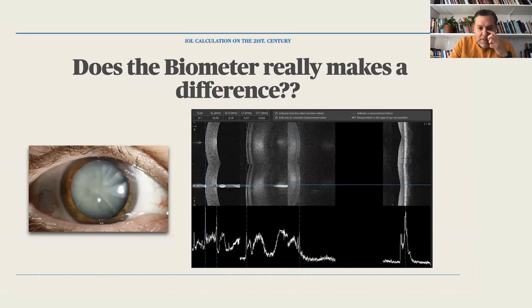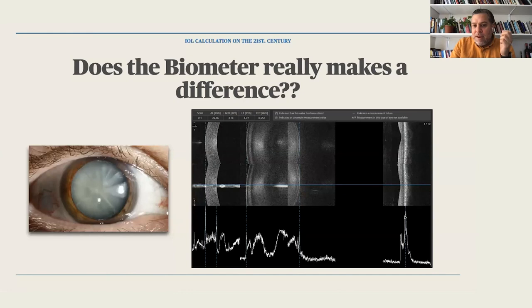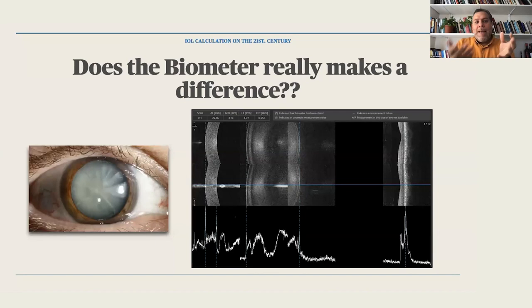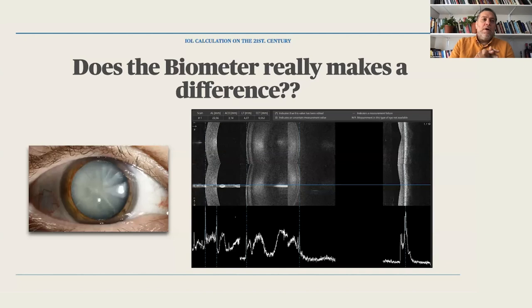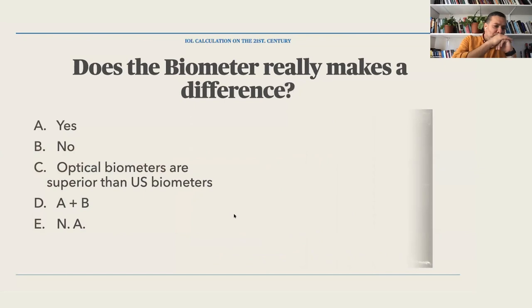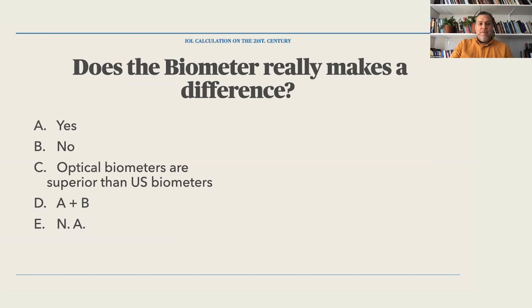When we come to hard cataracts and analyze the curves the biometer produces, if we can't get a good retinal signal because the cataract is so dense, the signal won't come through and we won't get reliable retinal measurements. The first corneal peak and the last retinal peak together account for the axial length. For mild or moderate cataracts any biometer should work, but for hard cataracts you need swept-source OCT, which has a greater wavelength to penetrate these opacities.